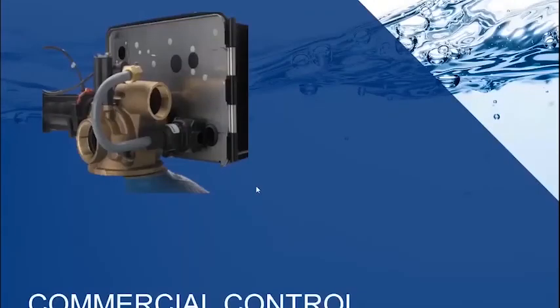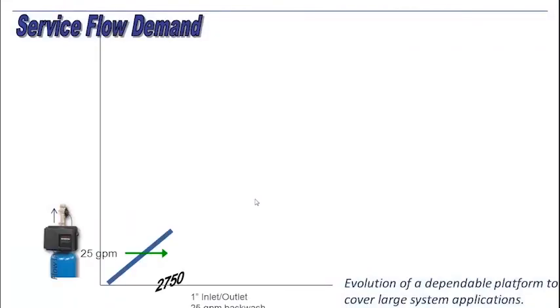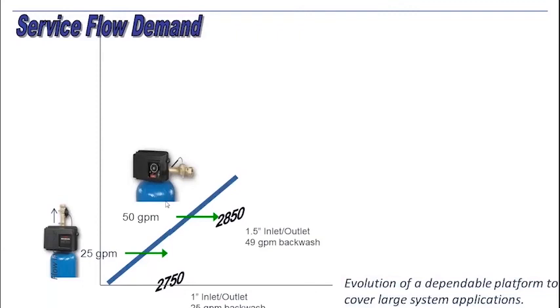These are our flex control valves, and there is a service demand profile order to these valves. We're going to start out with the 2750, which is a one-inch inlet and outlet. You have a 25-gallon per minute backwash and a 25-gallon per minute flow rate. That increases up to the 2850, which steps up to 50 gallons per minute with 1.5-inch inlets and outlets and a 49 GPM backwash. These filters can handle heavier medias like Corosex and BIRM.